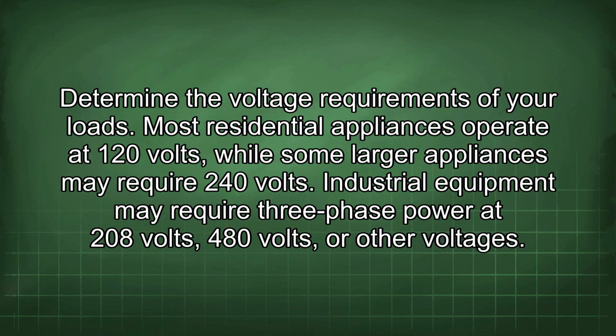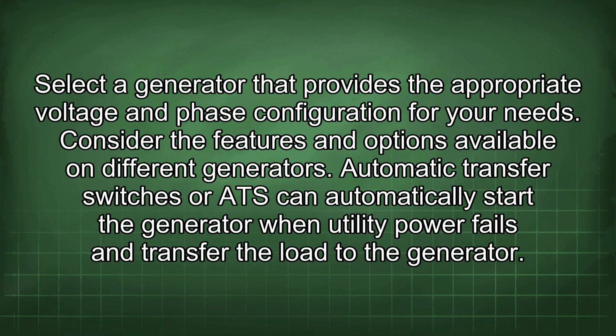Determine the voltage requirements of your loads. Most residential appliances operate at 120 volts, while some larger appliances may require 240 volts. Industrial equipment may require three-phase power at 208 volts, 480 volts, or other voltages. Select a generator that provides the appropriate voltage and phase configuration for your needs.